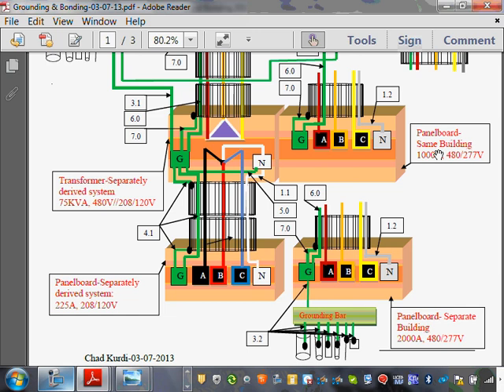This 4.1, believe it or not, is called the supply side bonding jumper, not an equipment grounding conductor. Why supply side bonding jumper? Because it's on the supply side of the separately derived system overcurrent protection device. Because you put a circuit breaker, you have to. Can I put, this is main lugs only? You have to put an overcurrent protection device right here, inside the panel or outside the panel. So you are on the line side of it, so that would be supply side. That's called supply side bonding jumper, exactly like the supply side bonding jumper at the service.